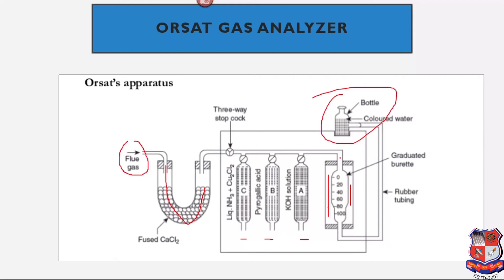When the water level in the reservoir rises, the flue gases are pushed from the burette into the first absorption chamber. The first valve is opened and the KOH solution absorbs CO2 from the flue gases. The remaining gas returns to the graduated burette, the valve is closed, and the water level is raised again. Next, the second valve is opened and pyrogallic acid absorbs the O2 content.